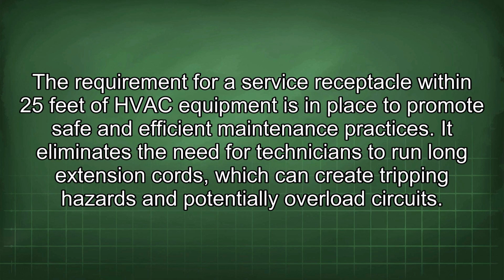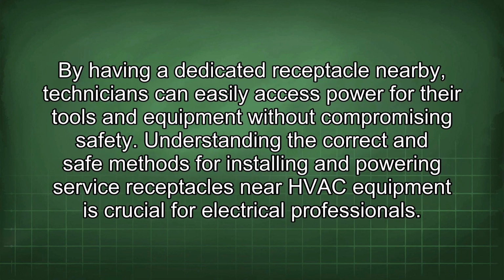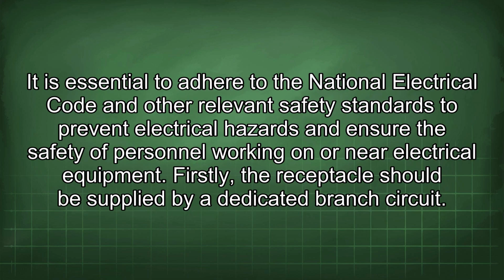The requirement for a service receptacle within 25 feet of HVAC equipment is in place to promote safe and efficient maintenance practices. It eliminates the need for technicians to run long extension cords, which can create tripping hazards and potentially overload circuits. By having a dedicated receptacle nearby, technicians can easily access power for their tools and equipment without compromising safety. Understanding the correct and safe methods for installing and powering service receptacles near HVAC equipment is crucial for electrical professionals. It is essential to adhere to the National Electrical Code and other relevant safety standards to prevent electrical hazards and ensure the safety of personnel working on or near electrical equipment.